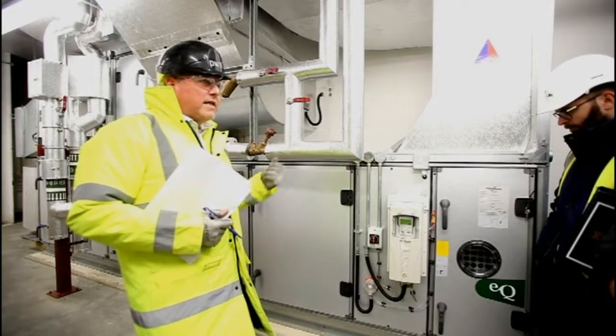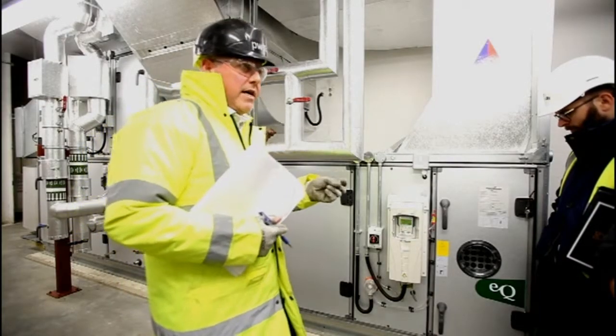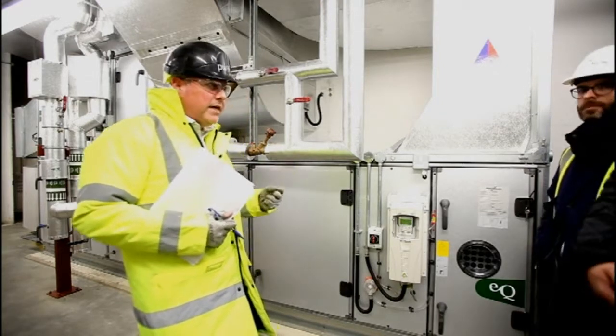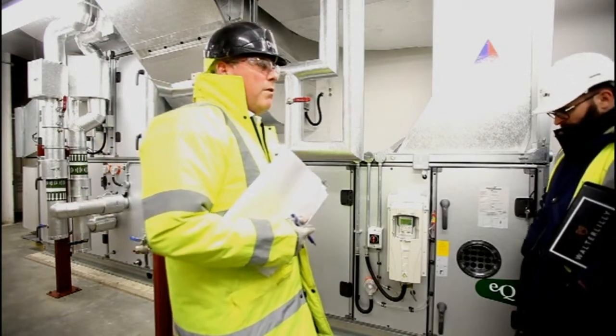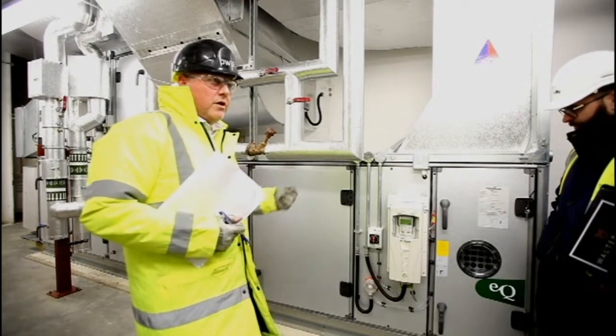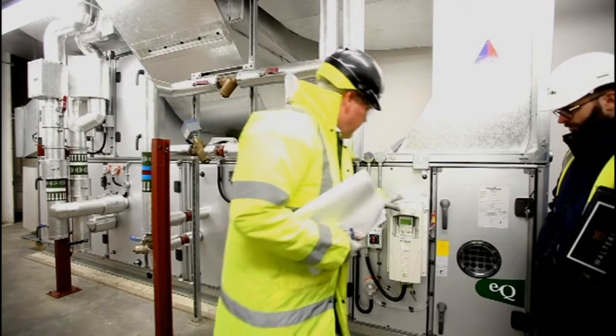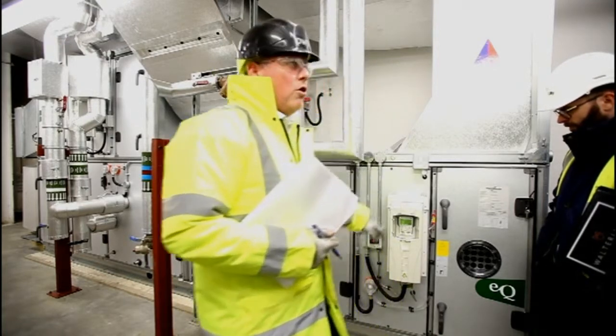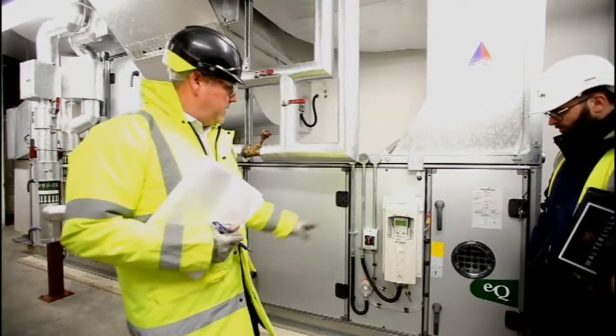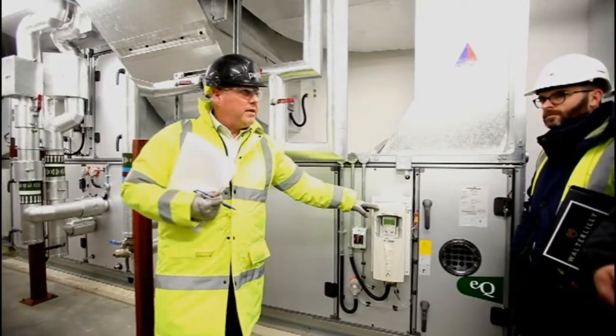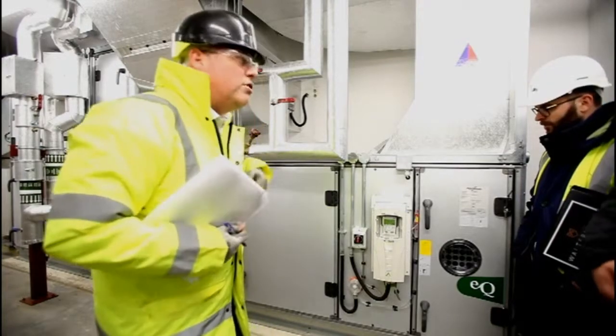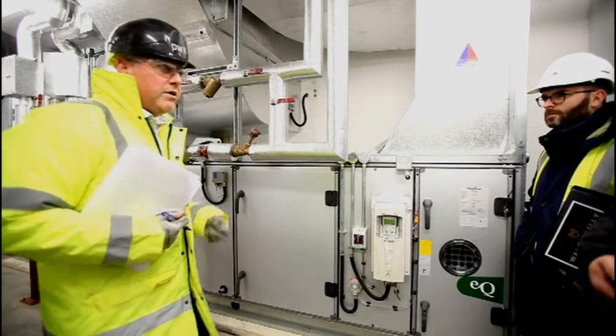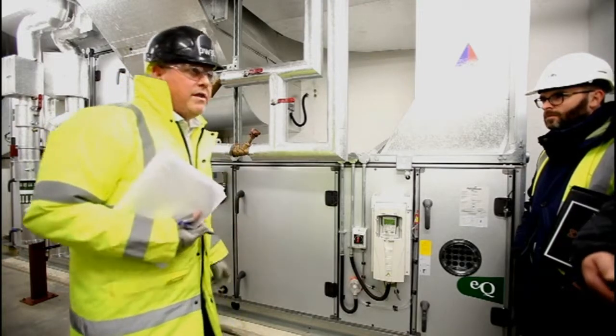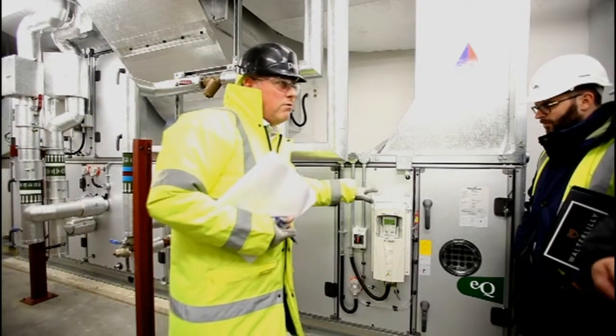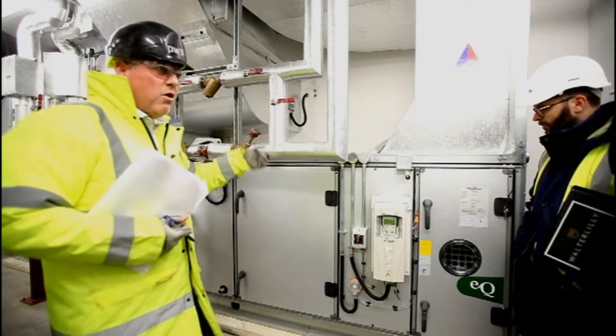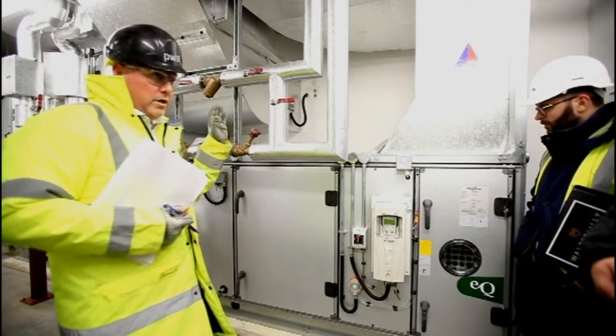On a night time, it is still aiming to maintain a certain temperature and humidity, but because there's less people in the building, we probably won't need as much airflow and air changes and oxygen in the building, for instance. So this will increase and decrease the speed of the fan automatically. It's an energy saving device. It's fitted to all of the major pieces of equipment. So basically, if there's no demand in the building, for instance, say we're up to temperature and there's enough humidity, the CO levels are okay in the room, then basically the fan will ramp down, like a trickle fan, just turn over, just keep the airflow going to a point.